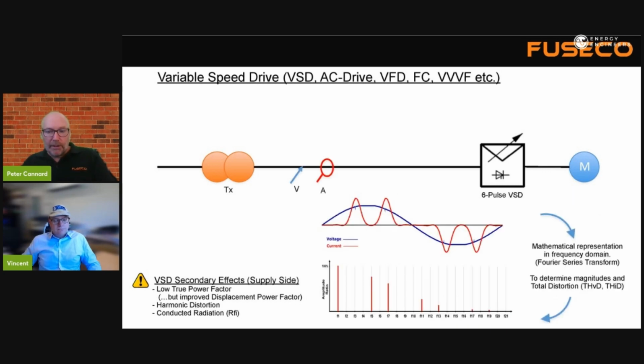Now, if we look at the other topic, harmonics, this proportion of true power factor that increases kVA, this whole topic is often referred to as a black art. It can be if you get into it long enough and in enough detail, but the fundamentals are reasonably straightforward. If we look at the red signal here, it's not sinusoidal and it's not in line with the blue voltage signal. So basically we have a lumpy and bumpy current waveform, and it's very difficult to understand for those that do understand the maths behind sinusoids and so on. We can't just use root 2 and peak to calculate what's what. It's really difficult to understand what's going on here.